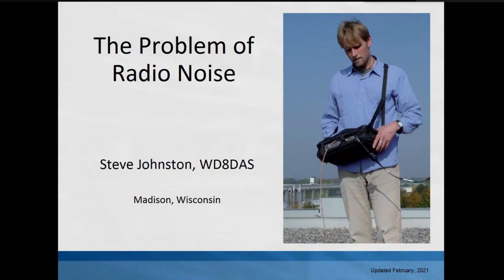Madison Gas and Electric, kind of a cooperative from the old days that's turned into a corporation now, serves power in this area, and they're also pretty conscientious about it. I had a crackling noise that was driving me crazy, so I went out in the dark of night with my portable radio and prowled around. I could see it peaking in different parts of the yards between the houses, and I realized that's where the underground utilities were running. I knew where the transformer was up on the hill behind the houses, and the underground feeders to each house fanned out from that point. I went up there and it was really loud right by the transformer, so I contacted them. They were out the very next day, understood what I was talking about, didn't brush me off, and found a cracked insulator on the high voltage side of that transformer that was periodically sparking.